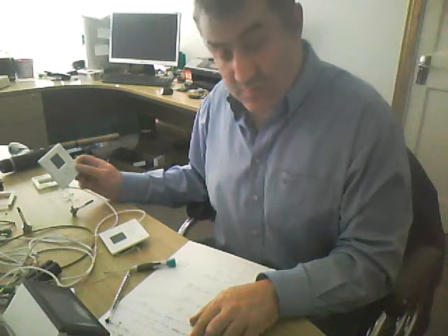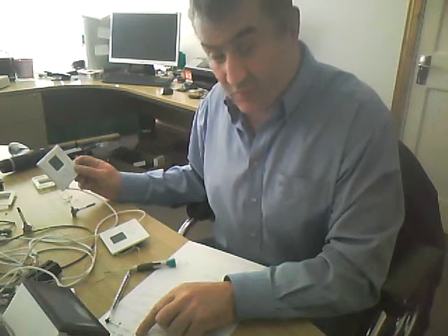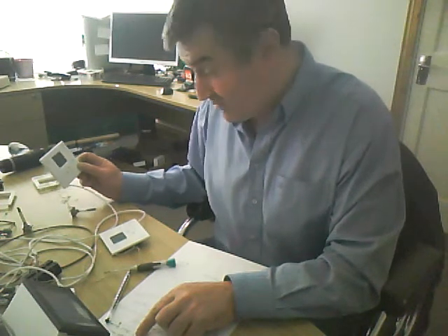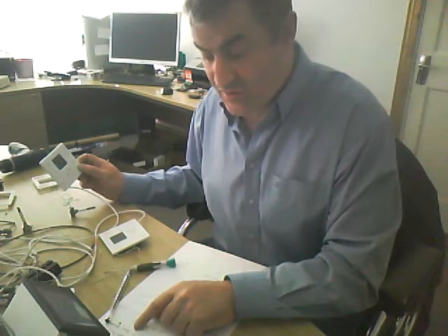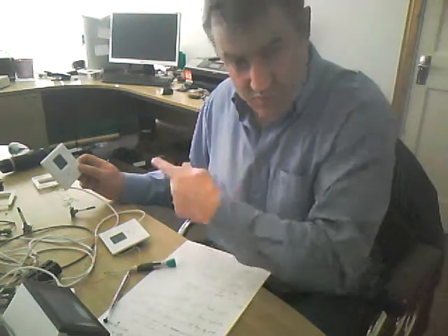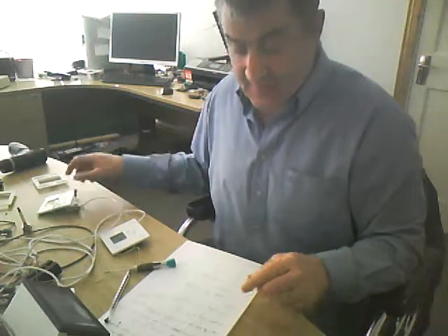You go into the engineering mode and you set the ST to 1. That's auxiliary type. That's the type of this guy, which would make it an auxiliary. And the SR, you set that to 1. That's the serial. That's in either 1 through 9 for the auxiliary sensors. We're only using 1, so it's 1 in this particular case. Your next step would be go to your environment and to your network and to set the number of auxiliary sensors that you have. It's normally set to 0, so you set that to 1.